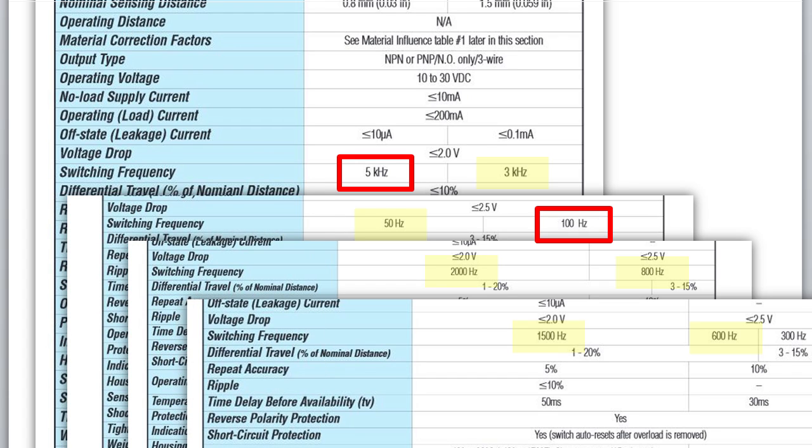So be sure that the switching frequency of the sensor is high enough to capture the objects you want to measure. I like for my switching frequency to be at least twice the rate of the objects I am trying to detect.